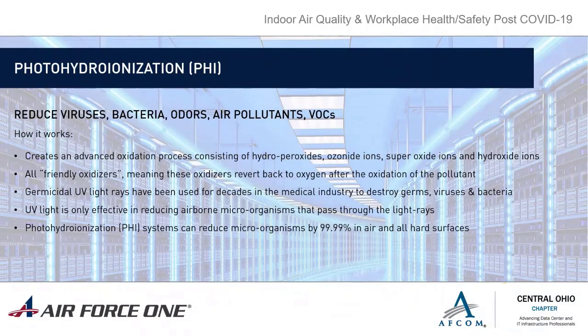I really want to touch on a piece here. I'm sure a lot of people on this call are familiar with UV lighting — it's been used for a long time in the medical industry and even in mechanical HVAC for point-of-use disinfection. Specifically, when used in the mechanical world, UV lights are installed with the bulk of their energy and light rays directed at the face of your cooling coil, because that's a wet coil, and being constantly wet through cycles it can grow mold, bacteria, and other contaminants. The UV makes sure that it stays disinfected.